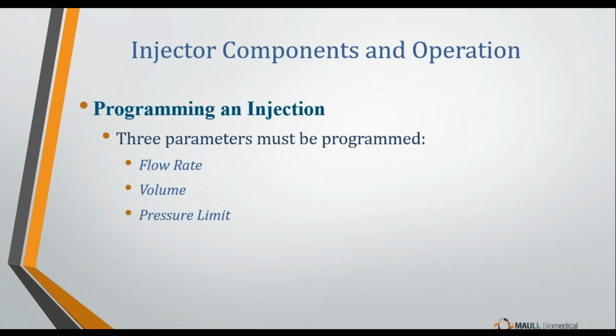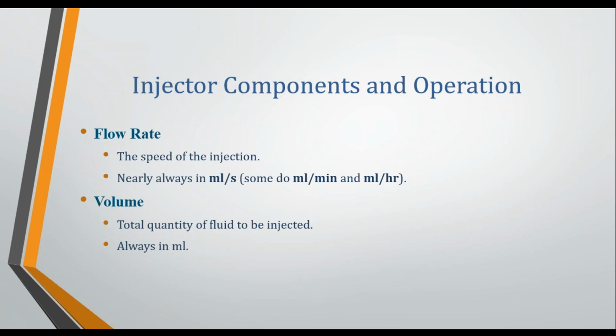Now we're actually going to get into the programming and injecting of the contrast fluid. When it comes to programming and injection, there are many parameters that the operator can select for a particular protocol when we want to perform an injection and inject fluid into the patient. There are many parameters that can be selected, but only 3 of them have to be selected. Everything else can be blank or have a 0 on it, but there are 3 parameters in a protocol that must have some value, and that is the flow rate, the volume, and the pressure limit. Now, the flow rate, and I'm just going to go over these so everybody's on the same page. I'm sure everybody's biomed, so I'm sure everybody's at least familiar with these terms, but we'll go over them just anyway.